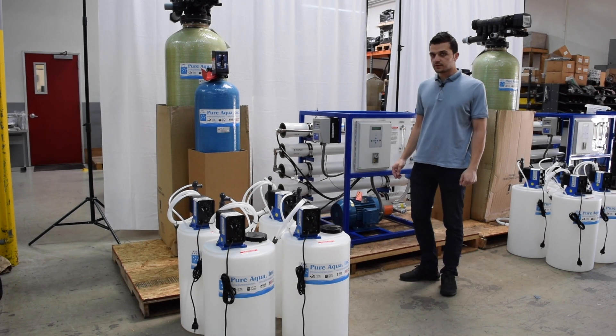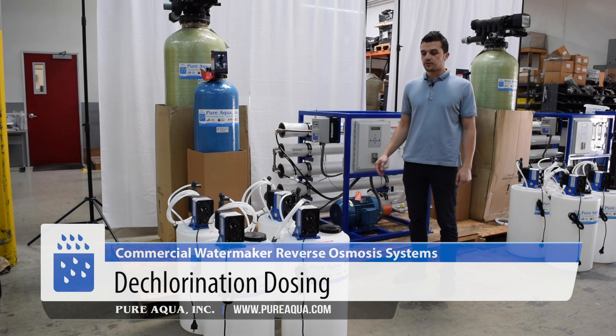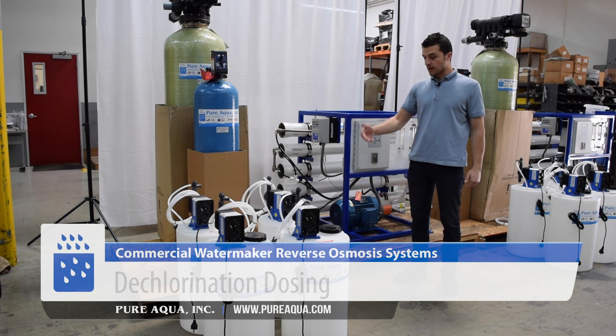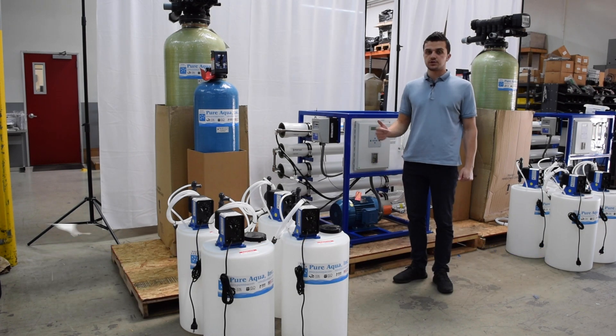After the multimedia filter, we inject the water with dechlorination chemicals, because you expect some residual — about half a ppm — after the multimedia filter. After the dechlorination chemicals are injected, we then inject with anti-scalant, and from there we feed into the RO unit.